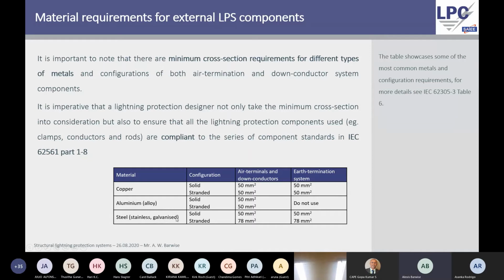Steel, galvanized steel as an example: when we use solid, we need a 50 mm squared air terminal, and for the earth termination, at least 78 mm squared. These are simple tables, so we know now the cross-section we would require, and we then only have to ensure that we reach a certain thickness in terms of the components used for air terminals, down conductors, and for the earthing system. Although the IEC speaks very clearly of using compliant components, so compliant components are components that are tested towards the 62561 series, part 1 to 8.